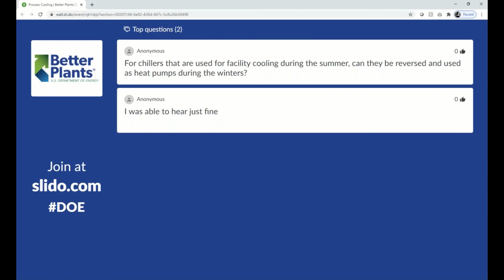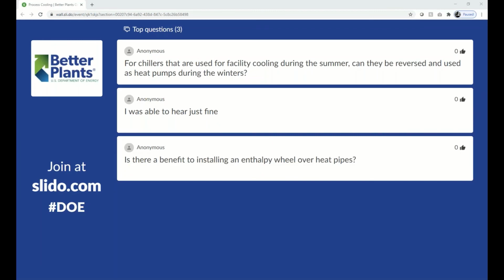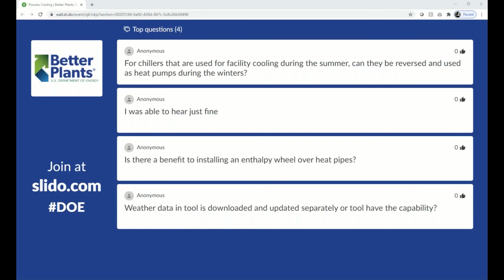For conventional chillers, for the chillers that right now you have in your facilities, which have a cooling tower attached, we cannot simply reverse that and use it as a heat pump, because for heat pump chillers, on the condenser side, the temperature is a lot warmer than the water you will get from cooling towers. That means the head for the heat pump chillers is very high. The compressors need to be designed to handle the big head. Typically for heat pump chillers, we use screw compressors to handle the big lift, but for the chillers we typically have in our facilities, we have both screw chillers and centrifugal chillers. So yeah, the answer is no. We need to buy chillers that are designed to run as heat pump chillers.